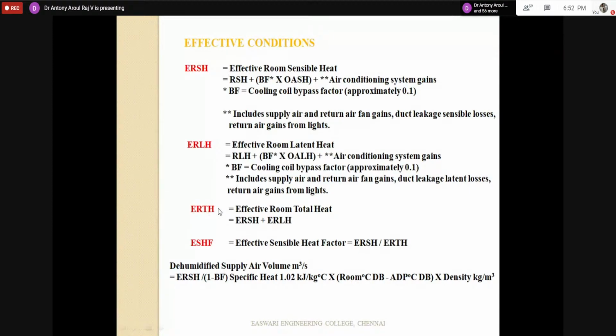and effective room total heat come into the picture. So we are calculating the effective room sensible heat factor, and using that, as well as choosing the bypass factor, we can calculate the bypass factor and ADP. Choosing the bypass factor, we have to calculate the effective sensible heat factor. We have to select the ADP, and we should be selecting a coil. So by that we can fix the bypass factor. From that we can calculate the dehumidified volume flow rate, that is, the supply air volume flow rate.